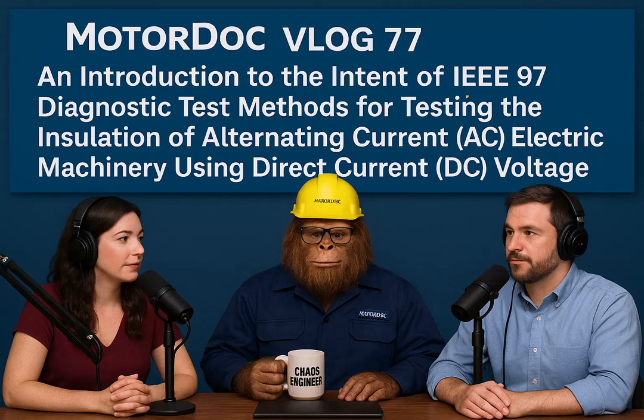Okay, so how do you put all this together to interpret PDC results for specific problems? Let's go back to moisture. Right. Moisture absorption shows up differently depending on the insulation type. For modern epoxy, high humidity tends to increase the polarization current, but the depolarization current might be less affected, or it might even show signs of drying out over the test duration. Interesting. What about older materials? For older materials like asphalt or polyester, both the polarization and depolarization currents tend to increase significantly with moisture. And this effect is often more pronounced in aged insulation, especially if there's some delamination present.